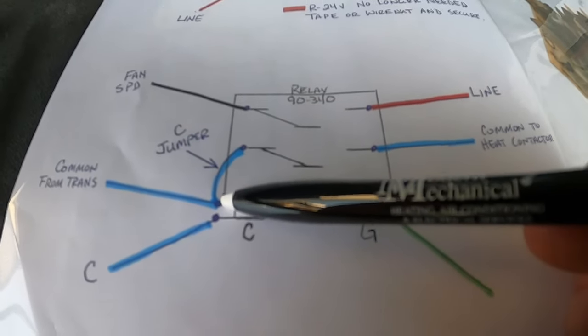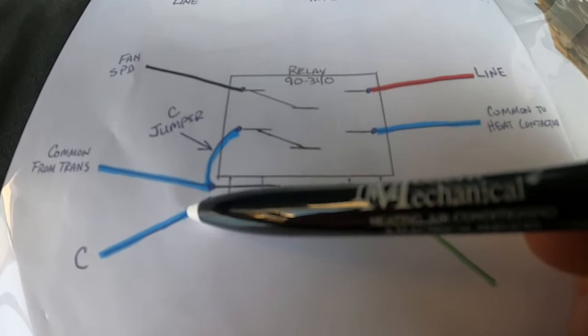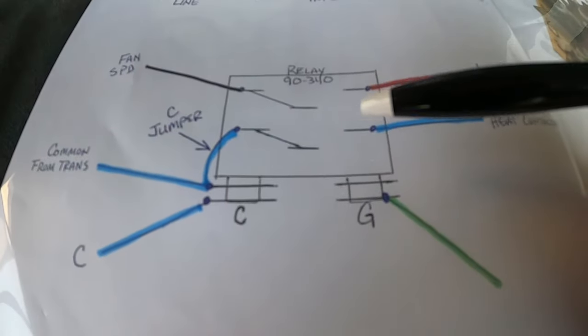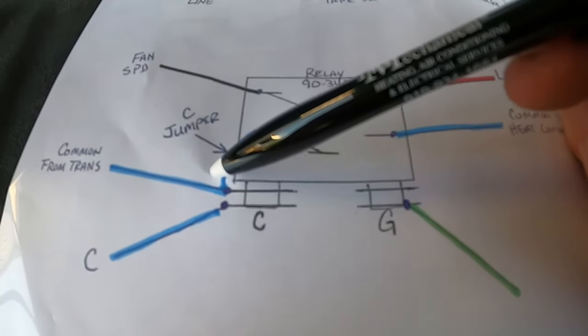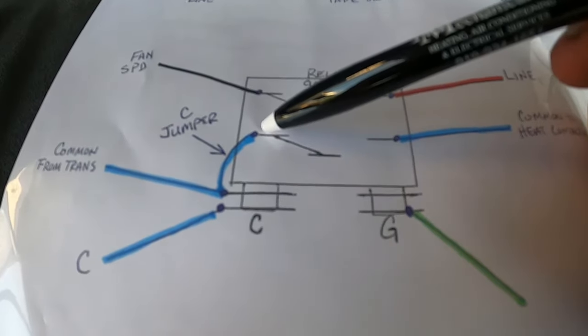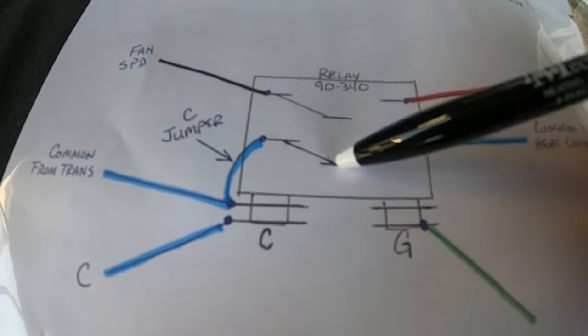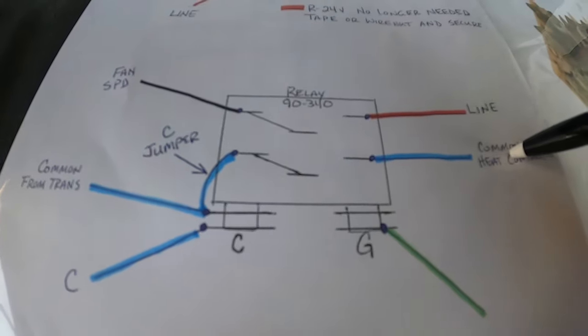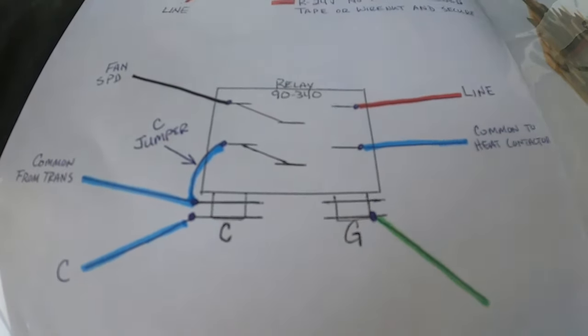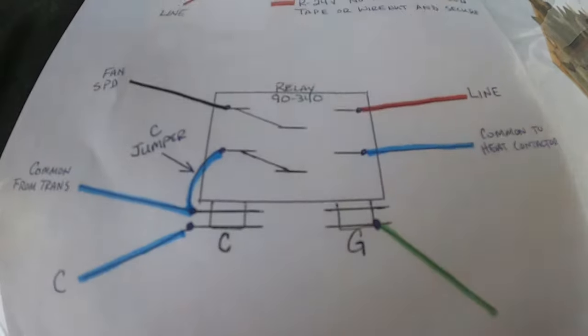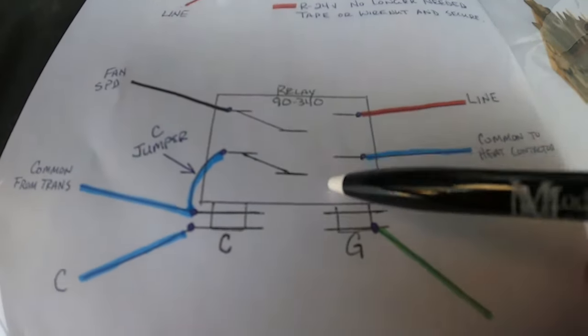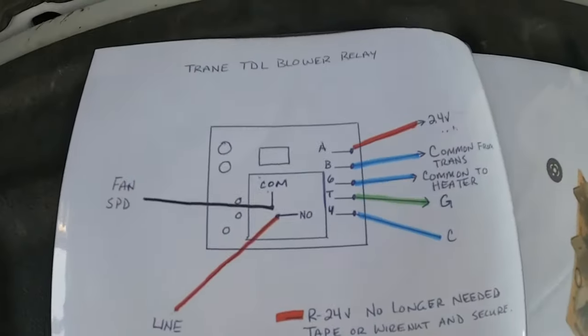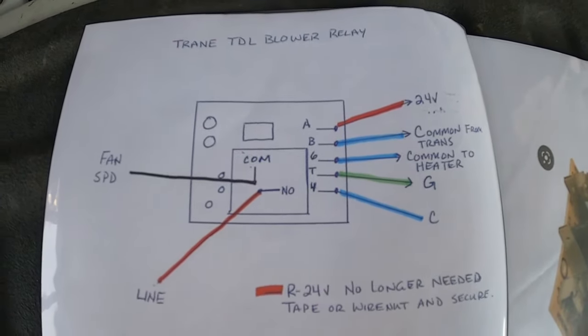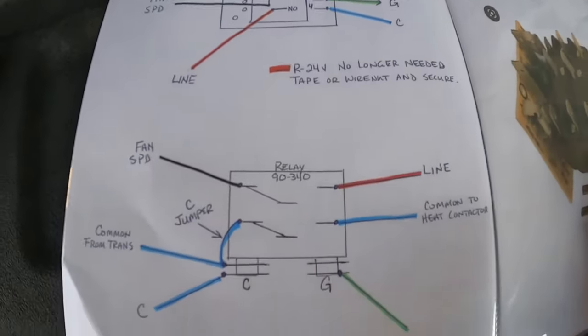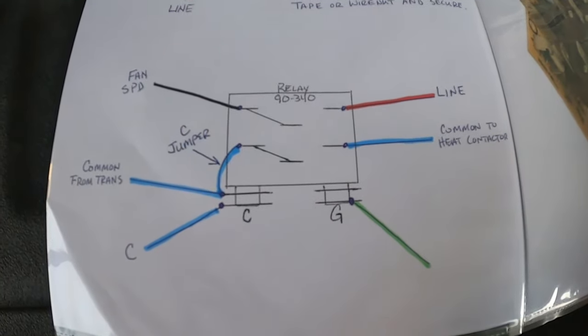You've got your common coming in from your transformer, and your common that's going back to your thermostat wiring, and then you're going to put a common jumper here to this common pole on this switch, so that when it closes, it sends common to your heat contactor, and then the heat strips will work if your relay is closed and you have airflow. So I've got everything color coded for that relay, and then I show them exactly where those wires go on the replacement relay, which is this.